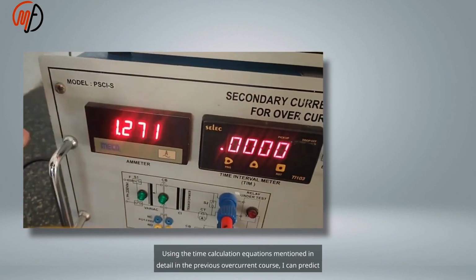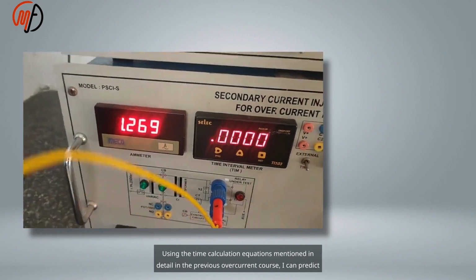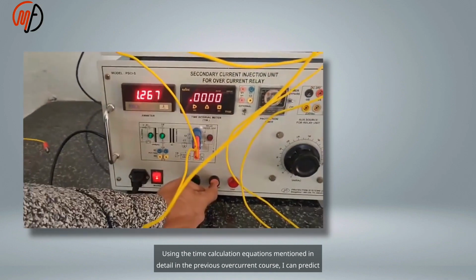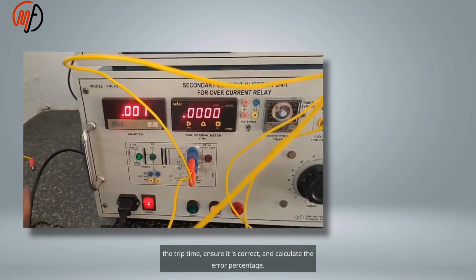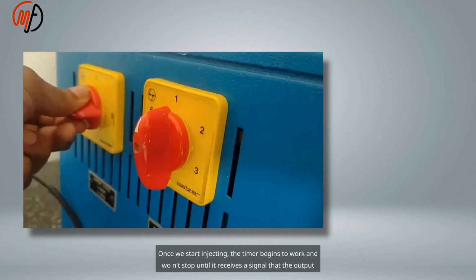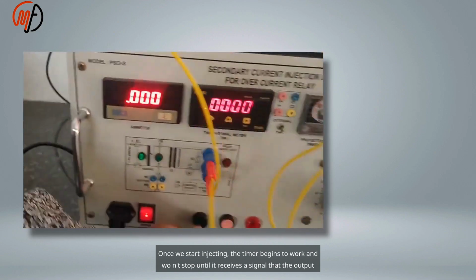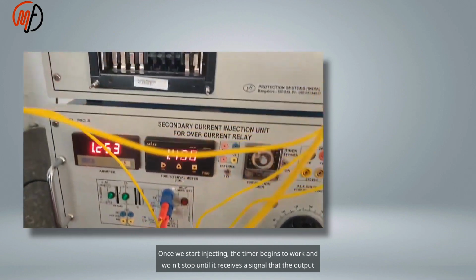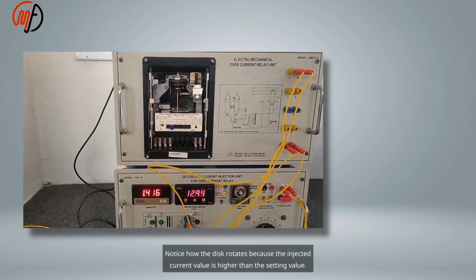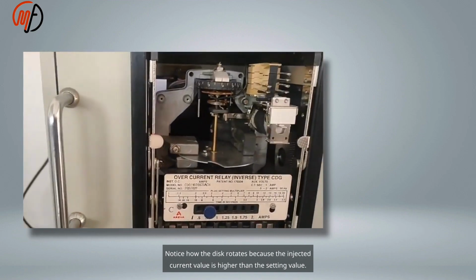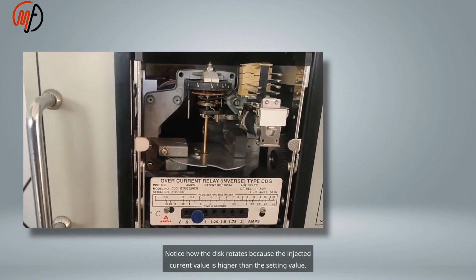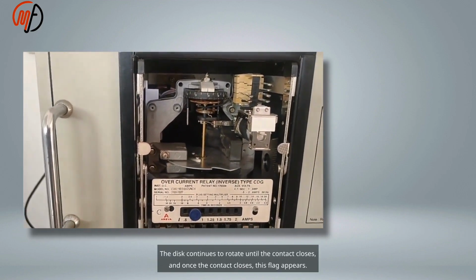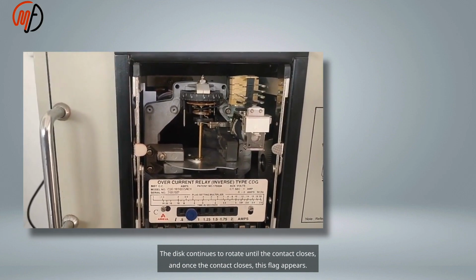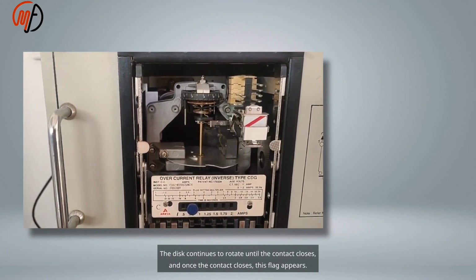Using the time calculation equations mentioned in detail in the previous overcurrent course, I can predict the trip time, ensure it's correct, and calculate the error percentage. Once we start injecting, the timer begins to work and won't stop until it receives a signal that the output contact has closed. Notice how the disk rotates because the injected current value is higher than the setting value. The disk continues to rotate until the contact closes, and once the contact closes, this flag appears.